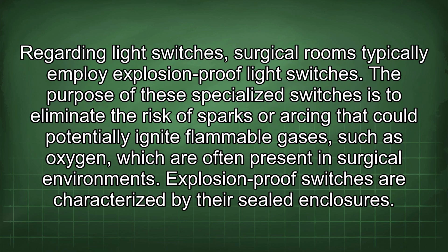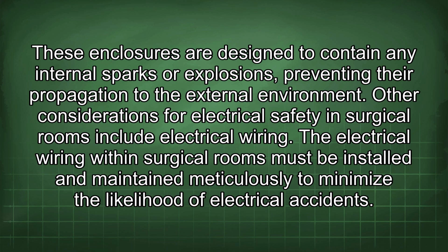Regarding light switches, surgical rooms typically employ explosion-proof light switches. The purpose of these specialized switches is to eliminate the risk of sparks or arcing that could potentially ignite flammable gases, such as oxygen, which are often present in surgical environments. Explosion-proof switches are characterized by their sealed enclosures. These enclosures are designed to contain any internal sparks or explosions, preventing their propagation to the external environment.